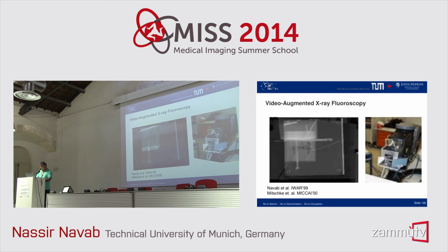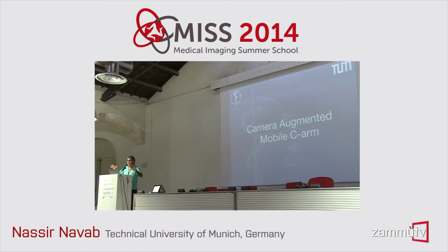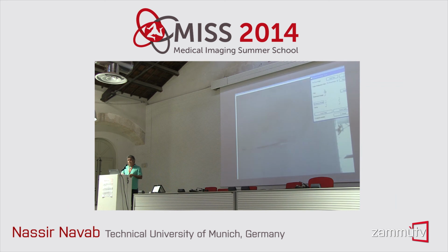Actually, Matthias Mitschke, my student, ran to Müller and got these mirrors for €5. We attached them in front of the camera and calibrated once forever with the camera. Then we had the very first images in which optics and X-rays were always co-registered. No need for registration. This is the same view. Unfortunately, big companies move very slowly.